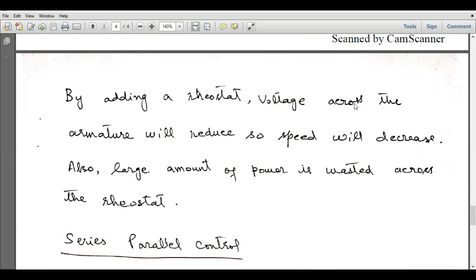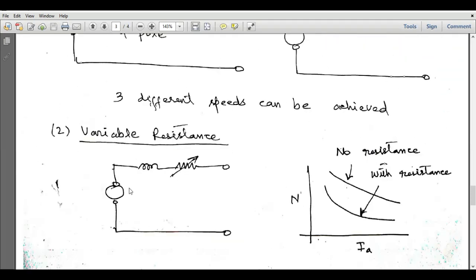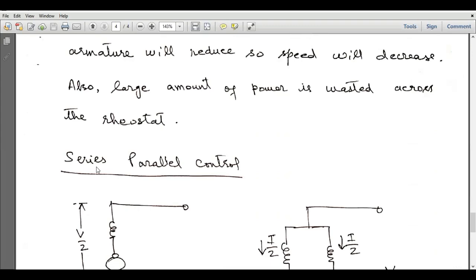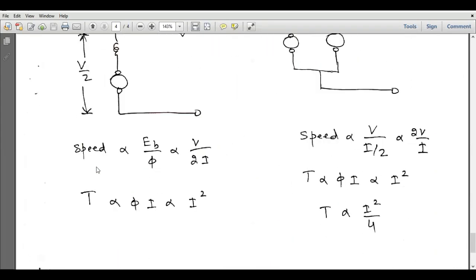By adding the rheostat, voltage across the armature reduces and speed decreases. However, a large amount of power is wasted across the rheostat, since the armature current is high and all of it flows through the variable resistor. This method is not favorable because it causes excessive power loss in the motor.